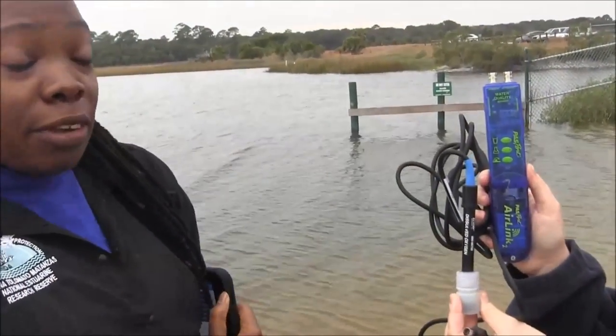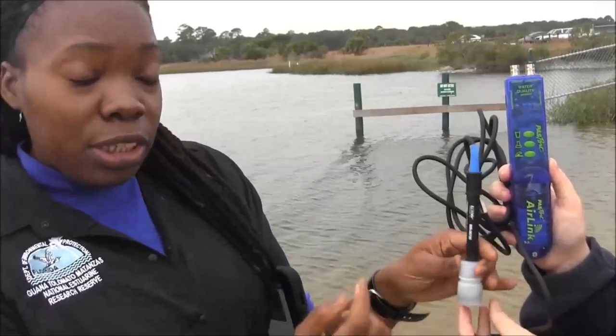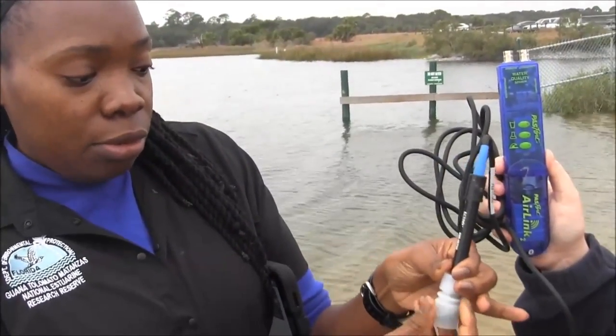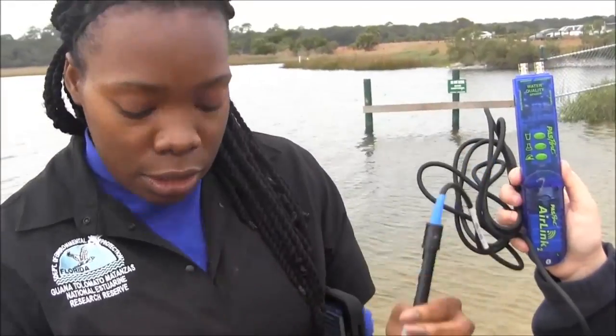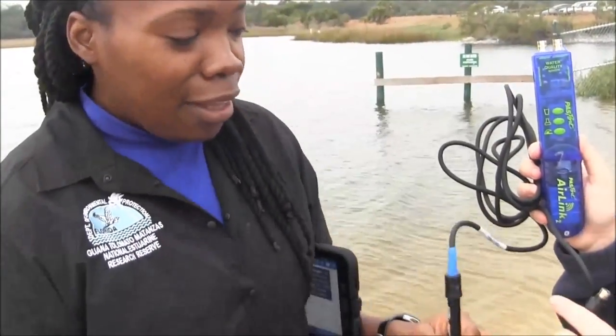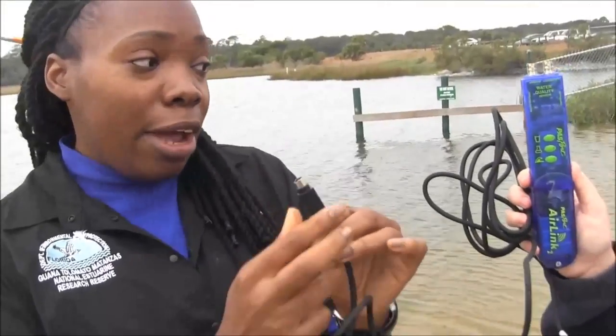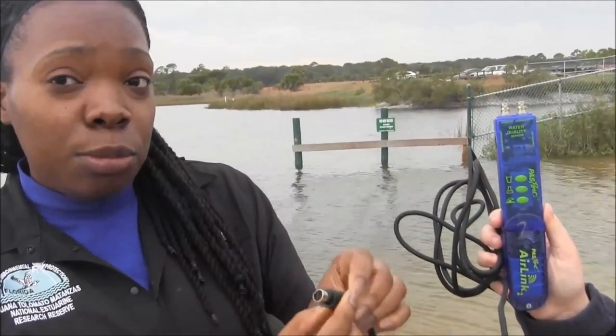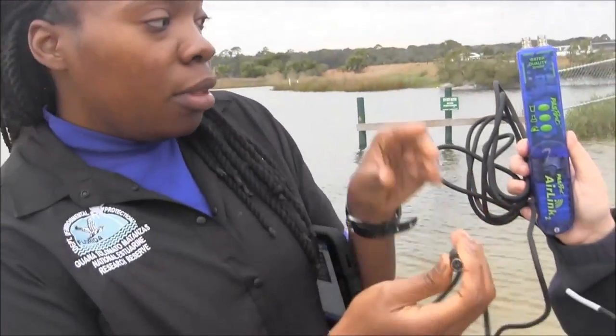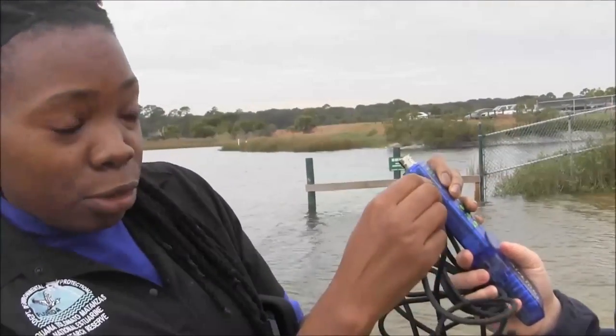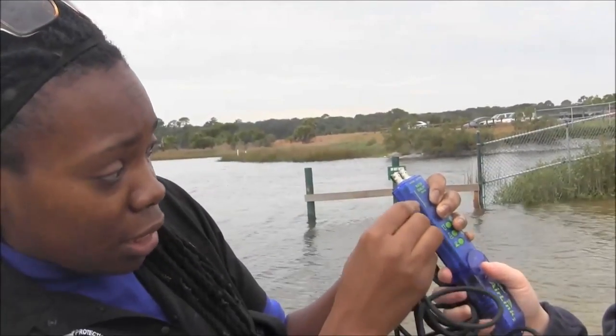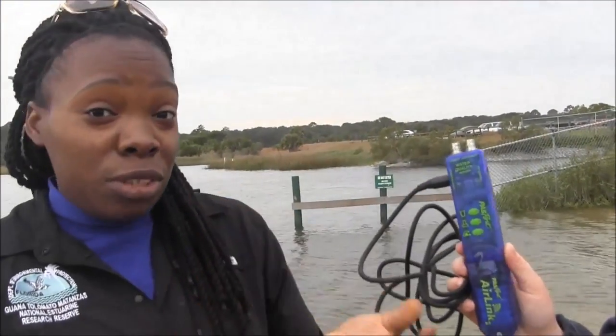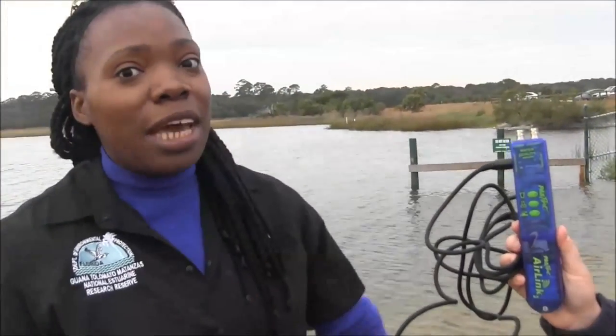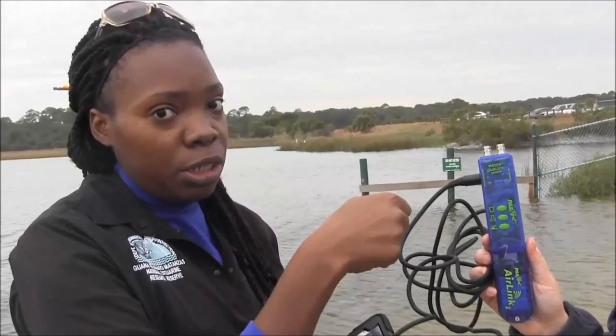All right, so you're going to do your dissolved oxygen reading now. Make sure, just like with the pH, you unscrew your vial. You want to keep this set aside so that the liquid doesn't drop out. When it's time to plug it into your actual sensor, make sure you pay particular attention to your prongs. It's just like with computers, you don't want to jam something in the wrong port. So you're going to make sure that you see how many prongs are at the top, and then line that up with the actual port that it goes into. So we're going to make sure it's on the right side, so it should plug in pretty smoothly and easily. If you have difficulty, please ask your instructor rather than just trying to push it in.